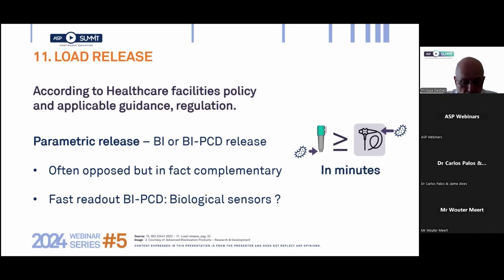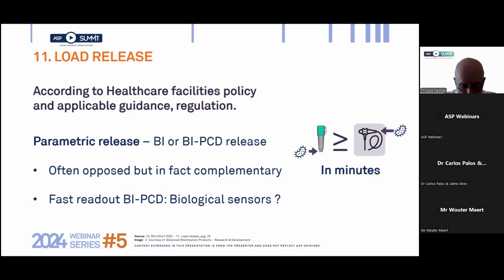First, because process parameters must always be controlled, and the use of a BI does not allow you to avoid the control of process parameters. Also, with the new generation of fast readout BIs or BI PCDs, the difference between electronic sensors installed on the sterilizers and biological sensors, which is what we could call the new generation of BIs, is becoming less and less. And BI PCDs with 15 minutes readout times could be considered as another kind of sensor attached to the sterilizer.